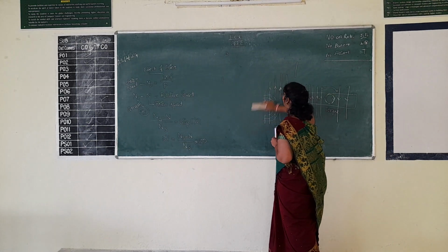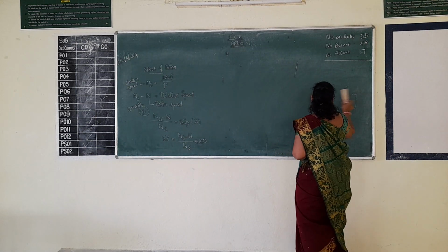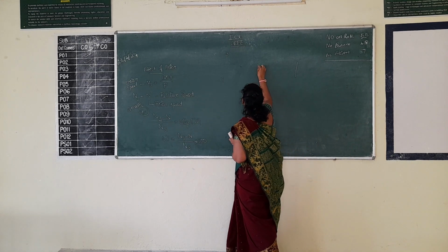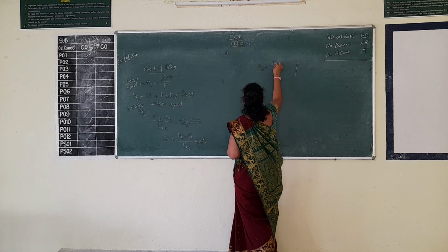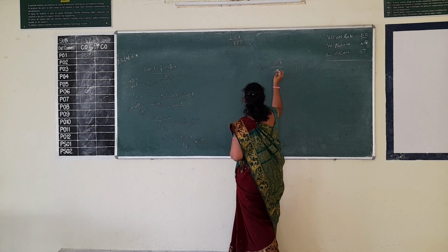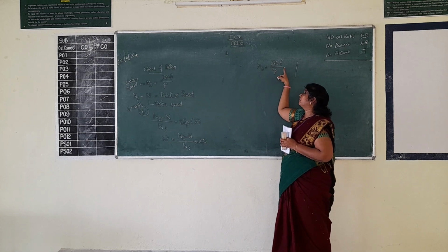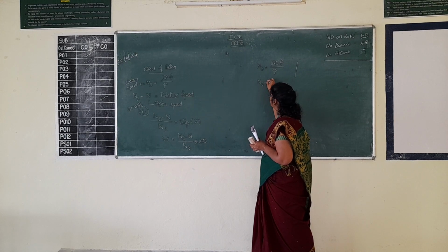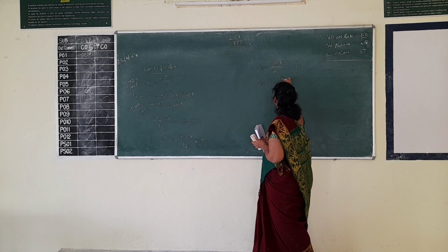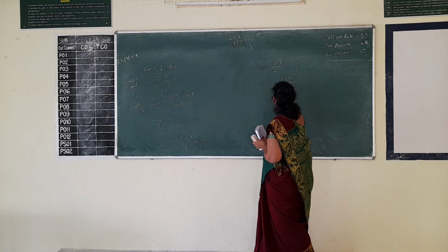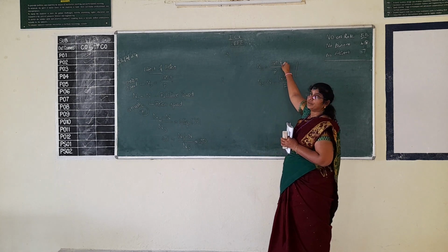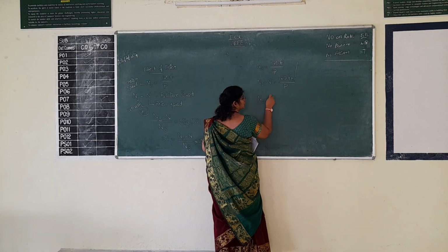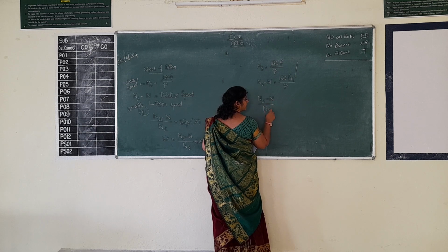So from that we are going to write effect of rotor. Stator speed Ns is equal to 120f divided by p. If we are considering relative speed, then your equation will become, frequency will be changed as fr, that is rotor frequency. We know slip is equal to Ns minus N divided by Ns.